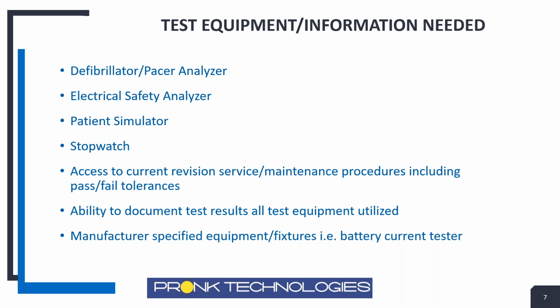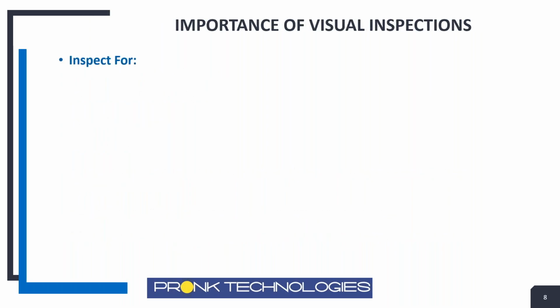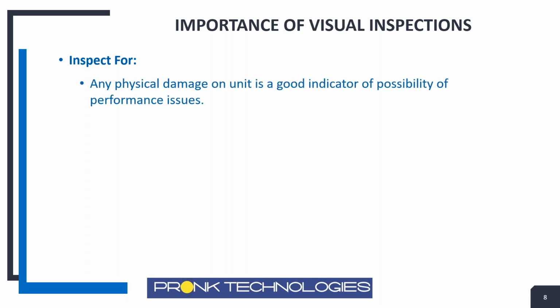The LIFEPAK is an example of one. They have a battery fixture they want you to use to do a battery compartment test. So there are some special test jigs that you have to either purchase or create on your own in order to do some of these tests. So they're not always the most straightforward things to check for. So of course, we've talked about it. Physical damage is the number one thing you hear and see on defibrillator analyzers.